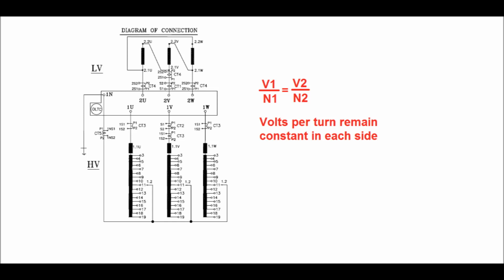That is, if the 1, 2 number selector switch is connected at the 3 number, then number 1 tap position will be selected, and if the 1, 2 selector switch is connected at 11 position, then the nominal tap position will be selected, and if the selector switch is connected to the 19 number, then tap position 17 will be selected. So there are 17 tap positions. By means of changing this tap position, the voltage can be regulated in the LV side.